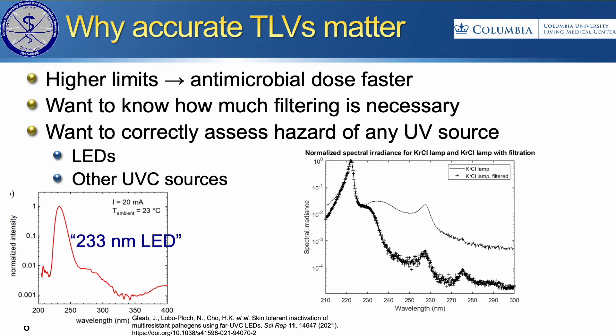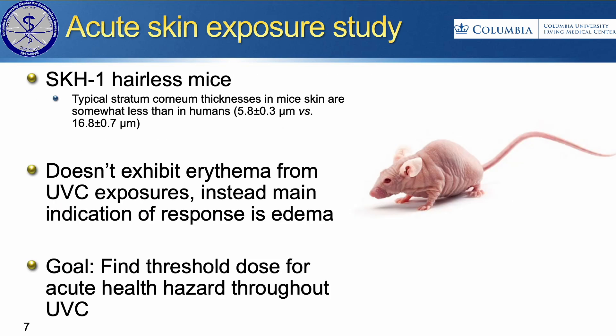Not all sources are going to be a perfect line source. We know that a krypton chloride lamp has emissions up to about 260 nanometers. LEDs being developed in the far UVC range also have tails that extend up to 230, 240, 250 nanometers. We need to know how much filtering is really necessary for those sources. Ideally, the TLV would be used to evaluate any lamp accurately — you would multiply the hazard factor at each wavelength by the total spectrum output and figure out the total health hazard.